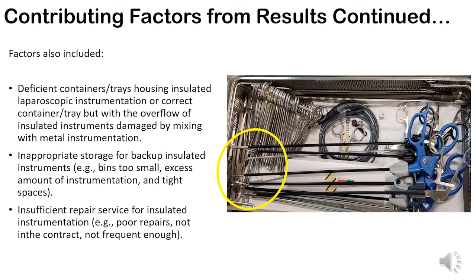To go on to contributing factors, there were deficient containers housing insulated laparoscopic instrumentation, or correct containers, but they had overflow of insulated devices on the bottom that were being damaged by the metal instruments. In this picture here, you can see that the distal ends of the insulated devices are actually being damaged. But if you look a little closer past where it's circled, you have towel clips that could actually cut into the insulation itself. There was also inappropriate storage for backup insulated instruments. For example, some of the bins were too small, or they had an excess amount of instrumentation, and they were in areas of very tight spaces.